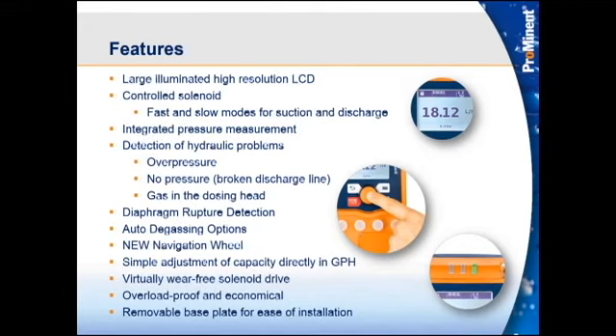You see this pump does have diaphragm rupture detection. That sensor is very similar to the same sensor we use on the Delta pump. It will screw into the back plate of the head, and then the cable will run to the front of the pump. If we were to detect a rupture of the diaphragm, that sensor would send a signal to the pump, and then we can program the pump to either give us a warning or an error. So we can have it either just give us a warning that tells us, hey, it's ruptured, but I'm still going to pump, or we can have a complete error which will shut down the pump. Now, if I have a relay equipped with that pump, that relay can send a signal out to somewhere where an operator wants to see it, and they'll be aware of that rupture, and they can fix that right away.